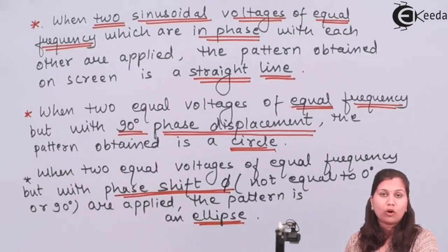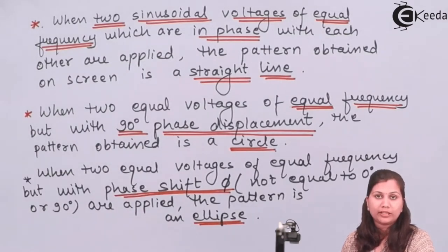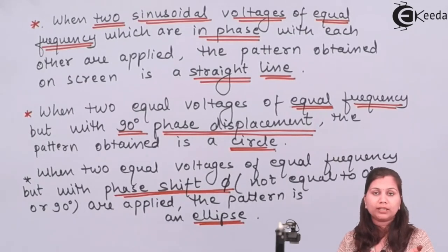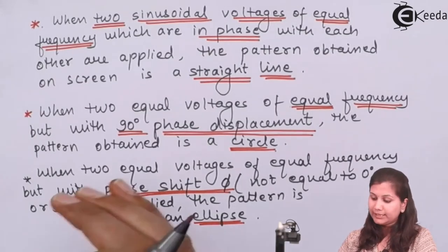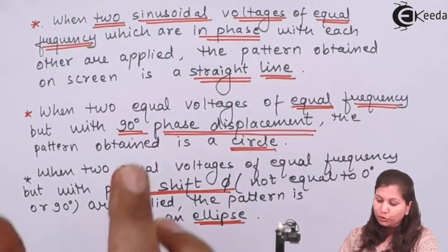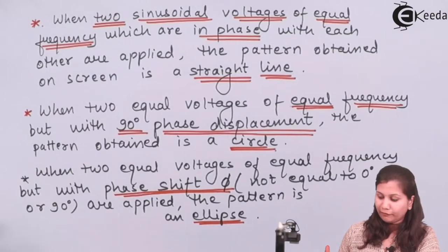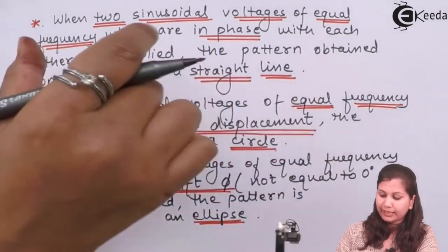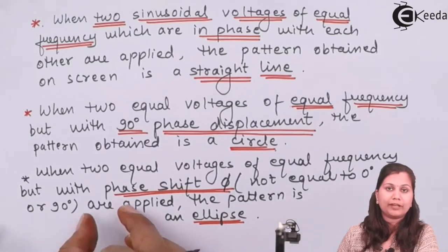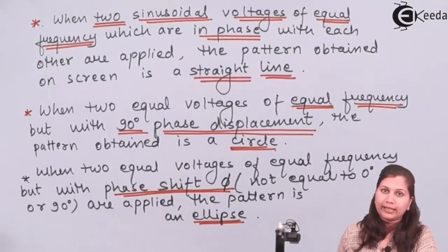These are the three types of Lissajous pattern observed when two sinusoidal voltages equal in magnitude and having the same frequency are applied to the vertical and horizontal deflection plates: a straight line, a circle, and an ellipse. Using this information, a conclusion can be made: if we obtain a straight line, the phase difference is 0; if we obtain a circle, the phase difference is 90 degrees; and if we obtain an ellipse, the phase difference is other than 0 or 90 degrees.